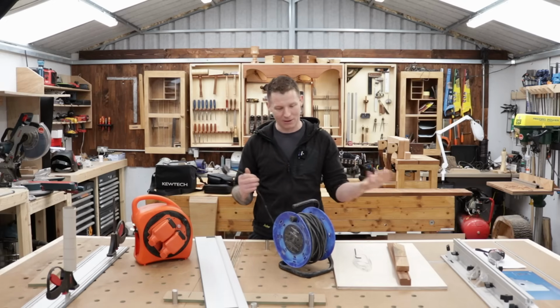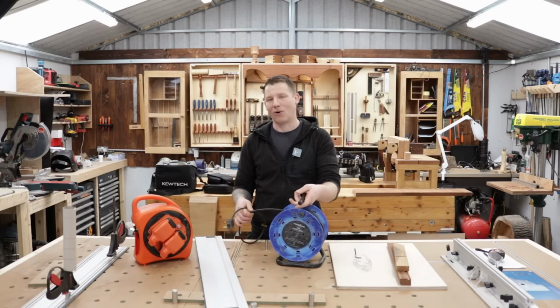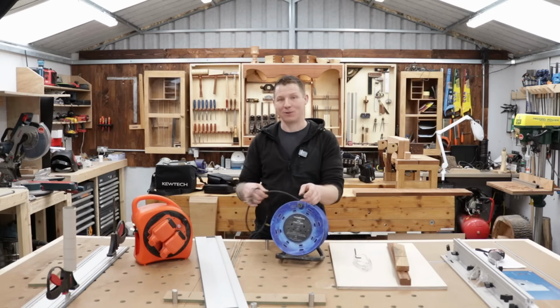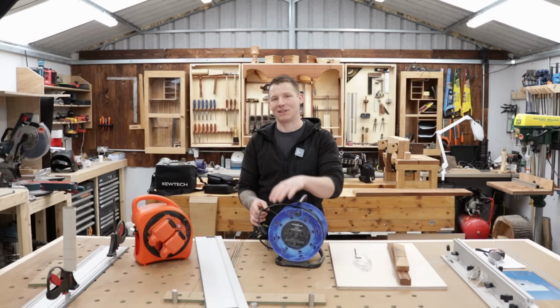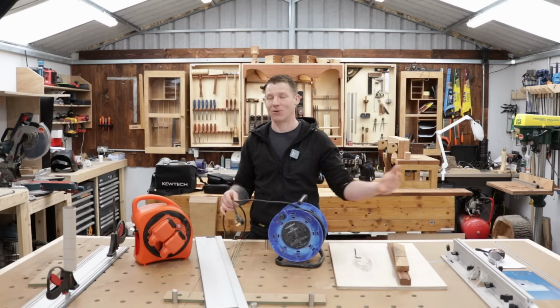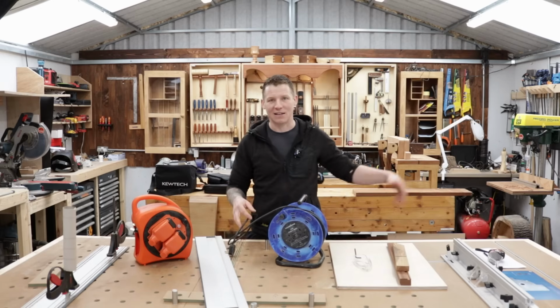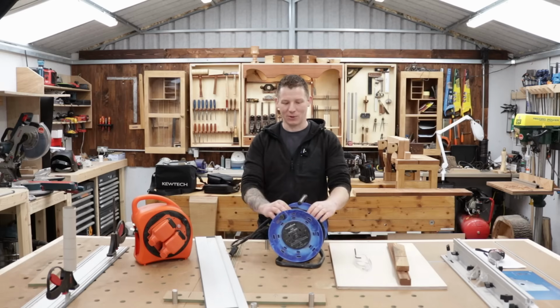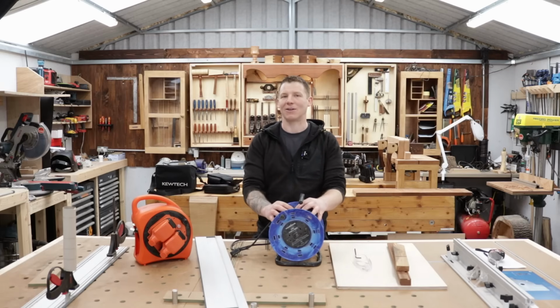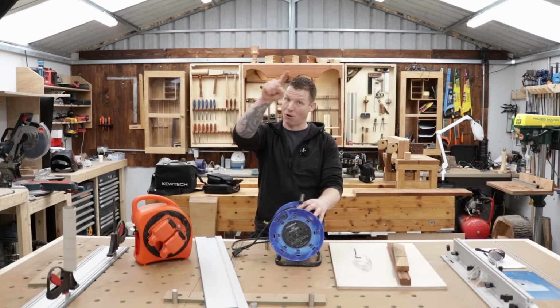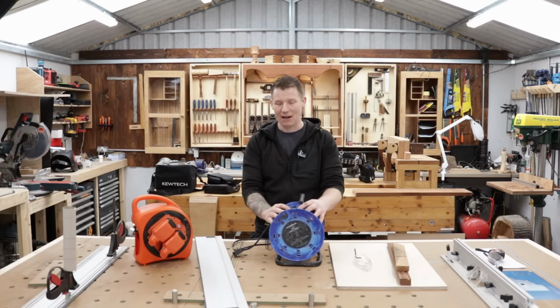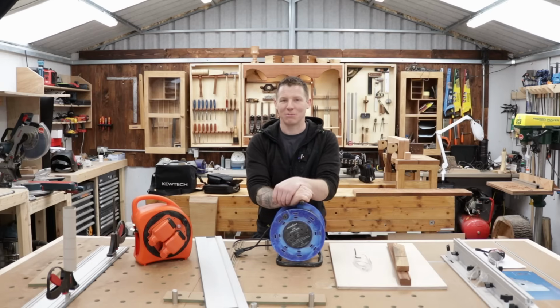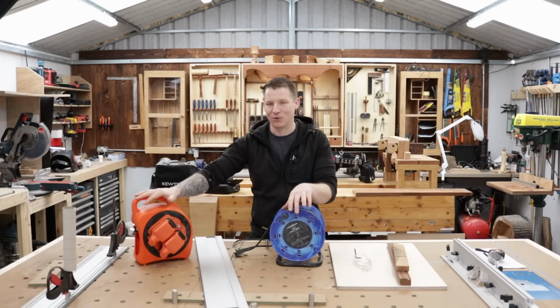They're good for a single use purpose, and always roll this cable out. So when you're using a drum type extension lead, roll out the full 20 meters, even though it might look ridiculous. You're dissipating that heat when it's all rolled out. Like I say, when the heat goes up in a cable, its current carrying capacity drops off, and it begins to drop off exponentially. So you can have a runaway situation. I've seen it before, believe me, and it's not pretty when it happens in a house. And you do not want to be turning the electrical cables in your house into a heating circuit. So that's just one thing to think about. That's why these things are only good for temporary use.